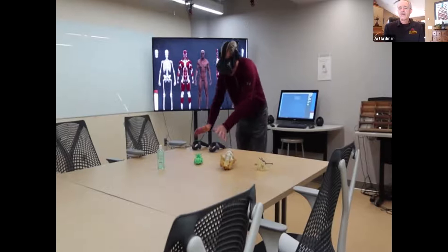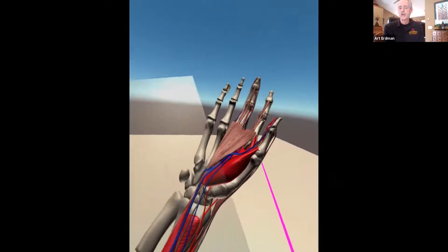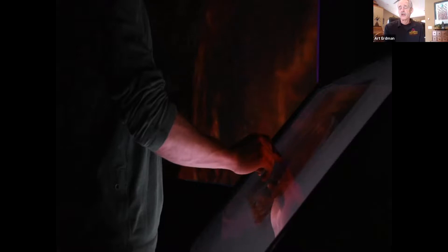We have various stored patient-specific anatomies — for example, a hand that we can slice through to see the vasculature. If you're doing a carpal tunnel device, we have the anatomy already. We can insert the actual device inside the anatomy and do the testing virtually. Our second generation system, developed in conjunction with computer science, allows us to study a portion of the heart with a lead in it and examine the effect of blood flow around that lead. With 3D glasses on, you would actually see the blood representation around the lead.